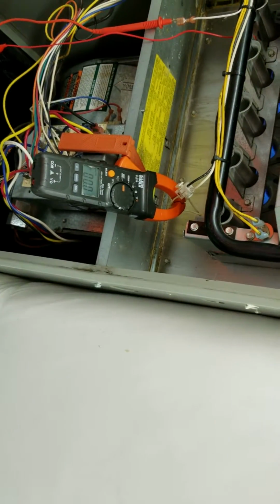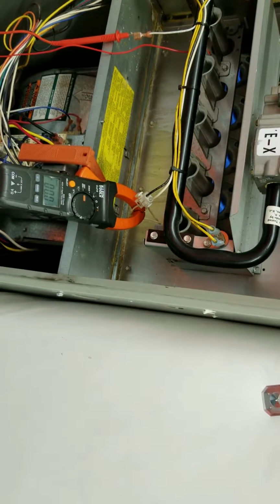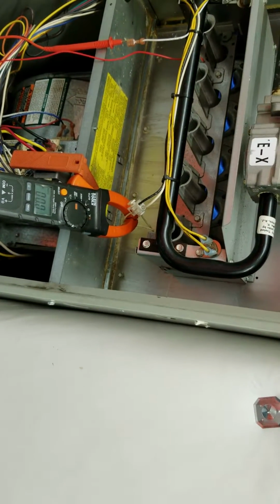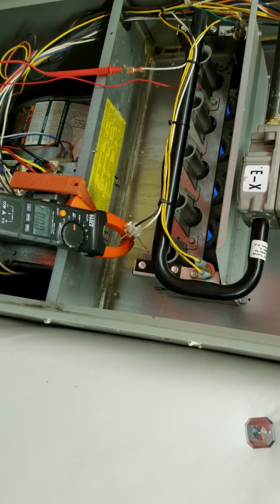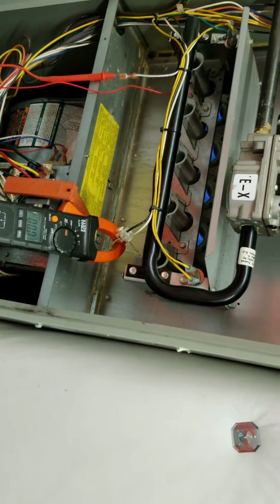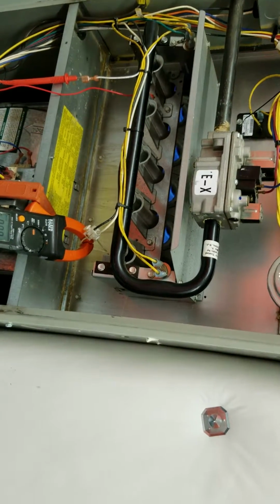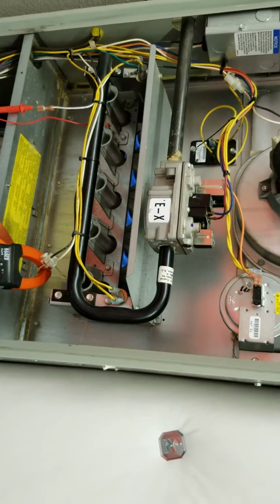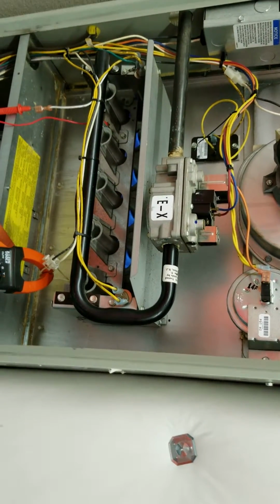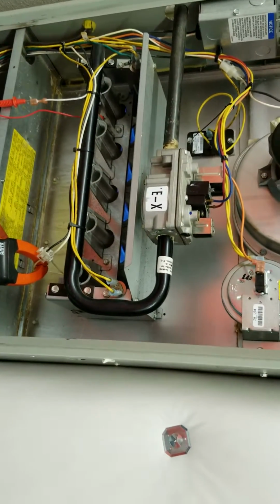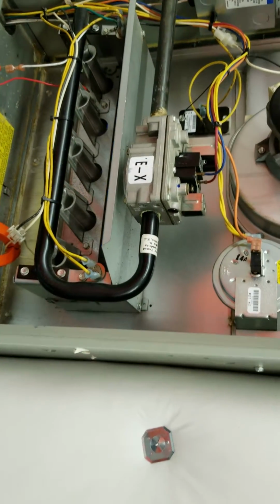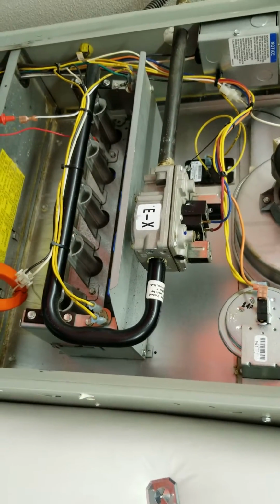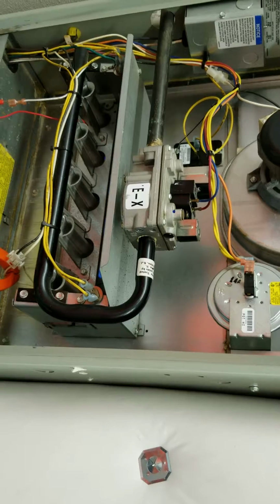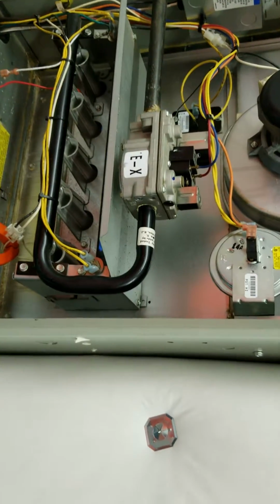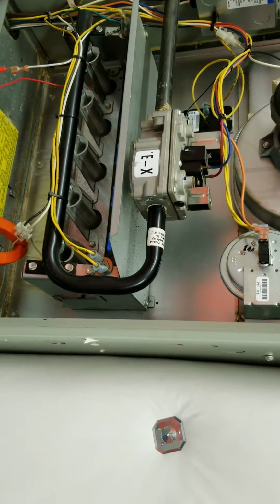And this type of sensor system has been used for probably close to 50 years on commercial applications or longer, and they've since adapted it to residential, because with the old thermocouple and pilot, if the pilot went out, that gas valve could stay open 3 to 4 minutes pumping gas into the building.